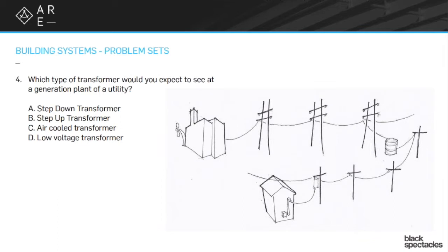I have a big distance to go up to, say, a 30th floor or 50th floor of a building. So on bigger buildings, instead of having those transformers outside, I may well have them actually stationed at different points through the building, inside the building, which can cause some interesting issues, right? I now have very high voltages moving through the building.